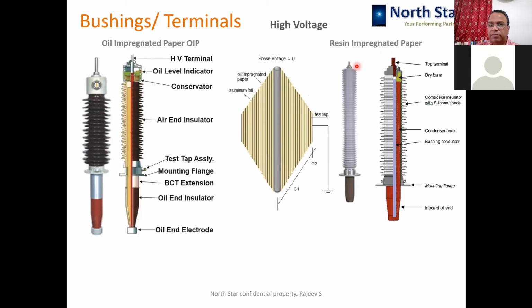On the contrary, RIP bushings, or resin impregnated paper bushings, are solid. There is no oil inside. There is a dry foam, and the composite insulation is filled in it. So they are maintenance free and very easy to handle. They are lightweight. Leakages are very little, partial discharge incidences are not that much, and they are actually maintenance free.